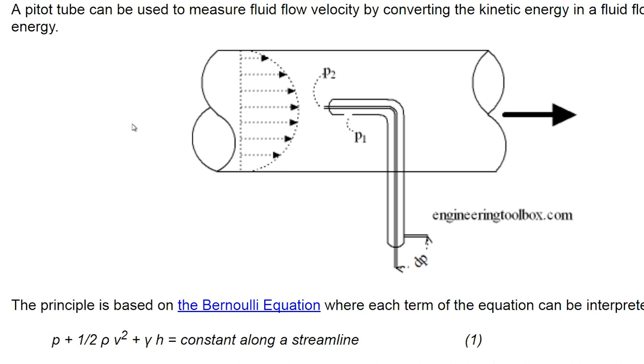For the last few weekends I was trying to build a pressure airflow meter based on pitot tube design. My goal was to obtain a stable reading proportional to the difference between stagnation and static pressure inside a ventilation duct. In a classic pitot tube, this pressure difference in Pascals can be used to calculate flow velocity from the Bernoulli equation.